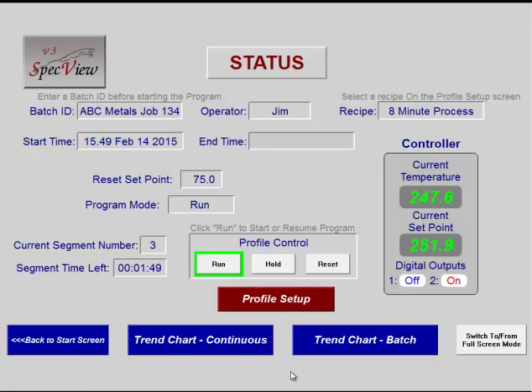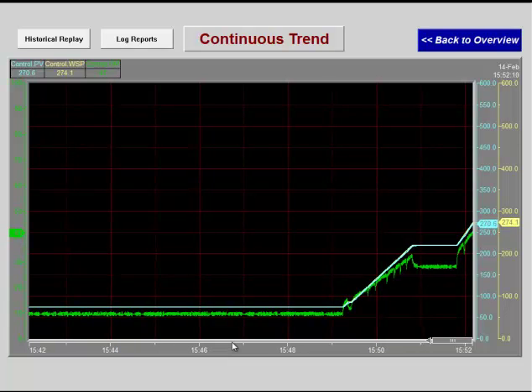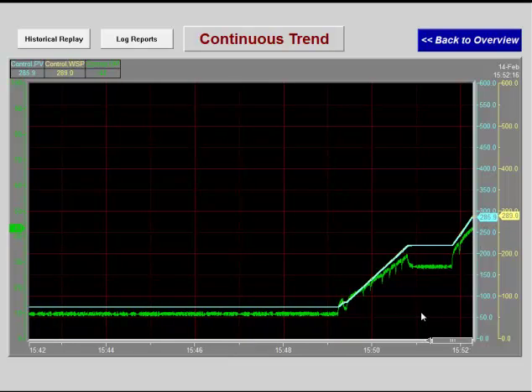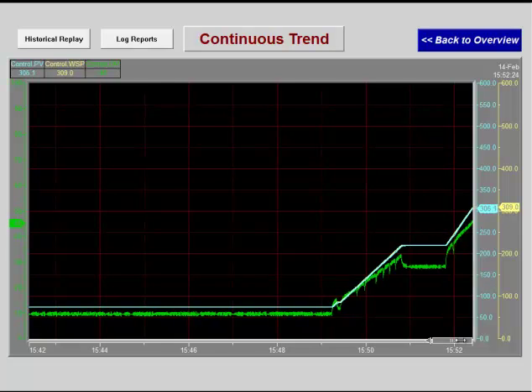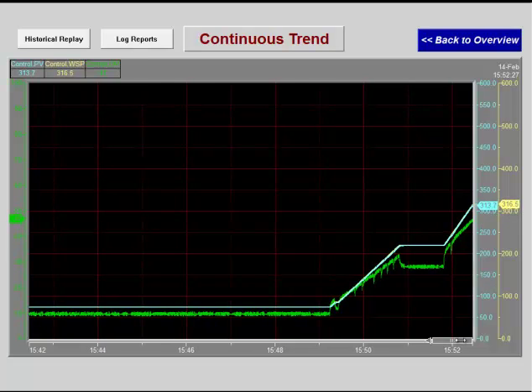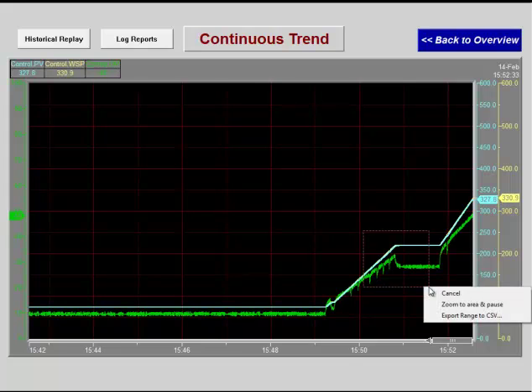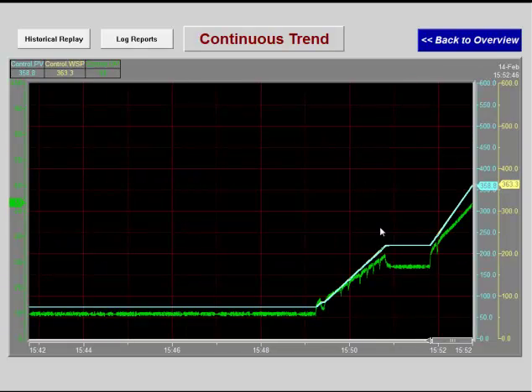This project shows two of the types of trend chart available in Specview. The continuous trend is set to a 10-minute time base and it keeps scrolling. There is a scroll bar that allows the chart to be scrolled back up to 10 screens — this feature is part of the historical replay option. Another feature allows the user to drag an area of the chart to either zoom or export the underlying data to a CSV file. Click on the chart and select Back to return to the normal chart.